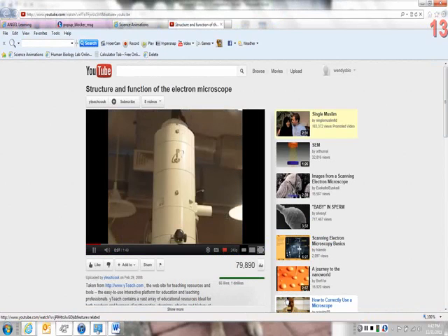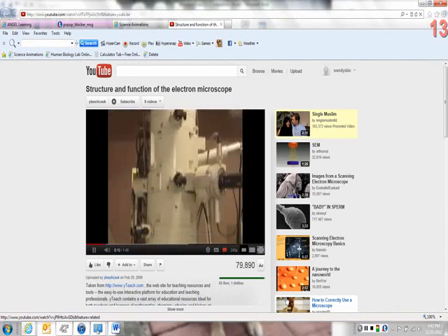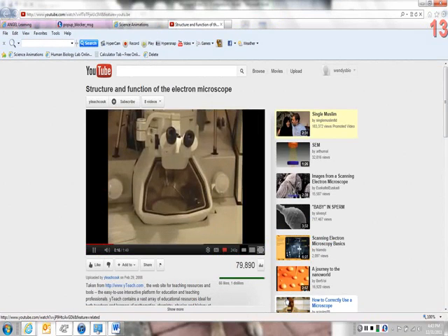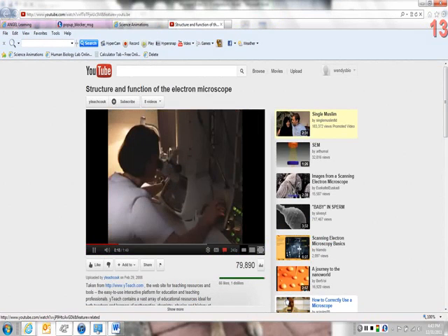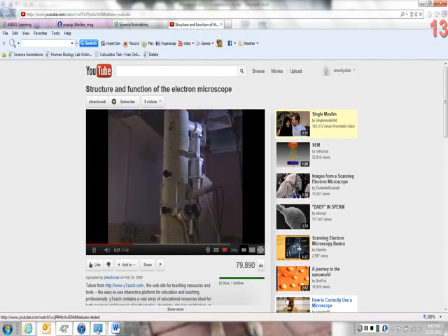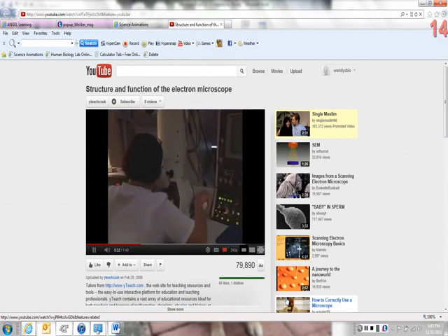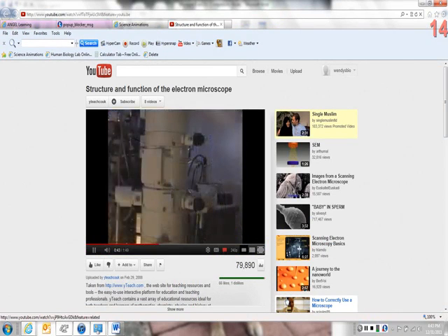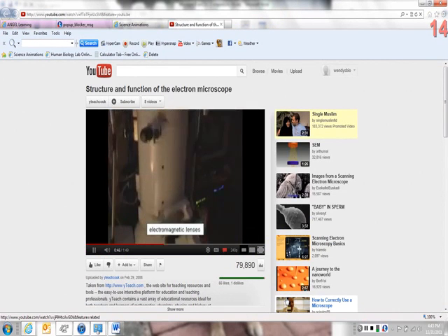The electron microscope consists of a cylindrical tube about 2 meters long, which is completely devoid of air. In contrast to the light microscope, the electron microscope visualizes objects using a thin beam of rapidly moving electrons that interfere with the specimen placed in the tube. The electrons are emitted by the cathode at the top of the tube and then accelerated by the anode. They then pass through a small aperture, which forms them into a beam, and into the vacuum inside the tube. The part of the microscope that generates the electron beam is sometimes called the Electron Gun.